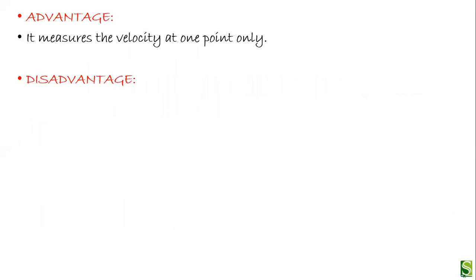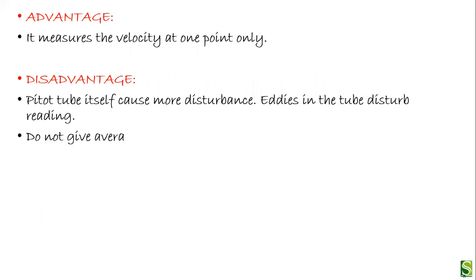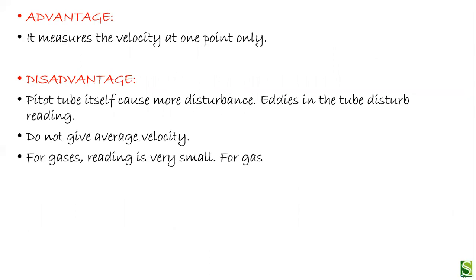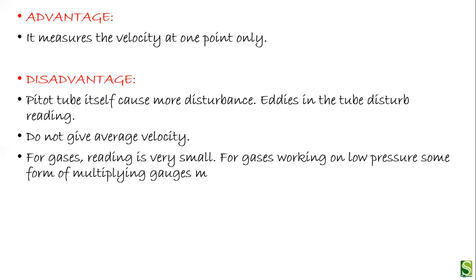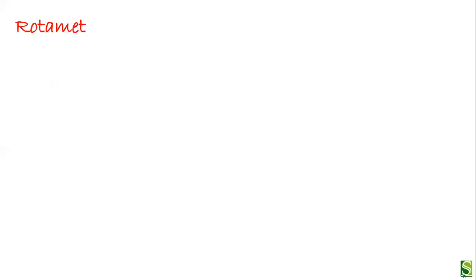Disadvantages of the pitot tube: the pitot tube itself causes disturbance, eddies in the tube disturb the reading, and it does not give average velocity. For gases, the reading is very small, and for gases working at low pressure, some form of multiplying gauges have to be used.